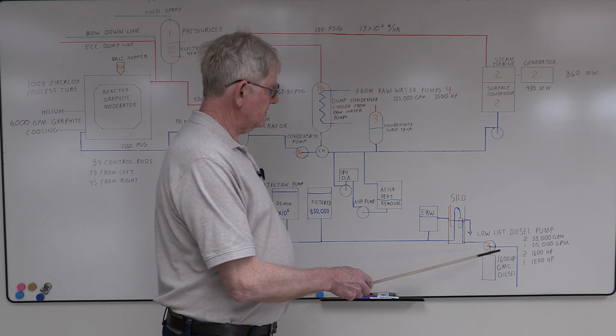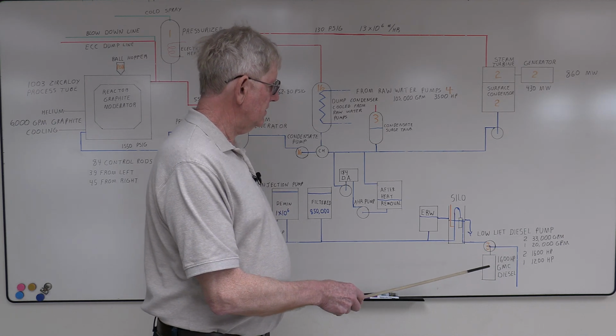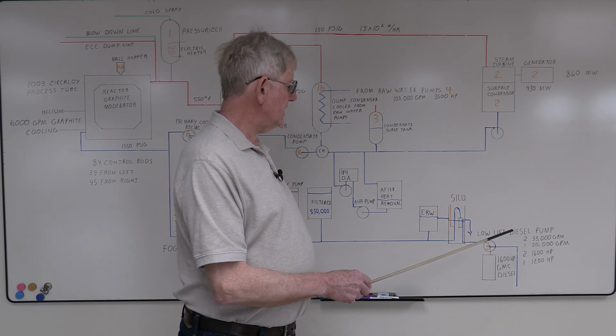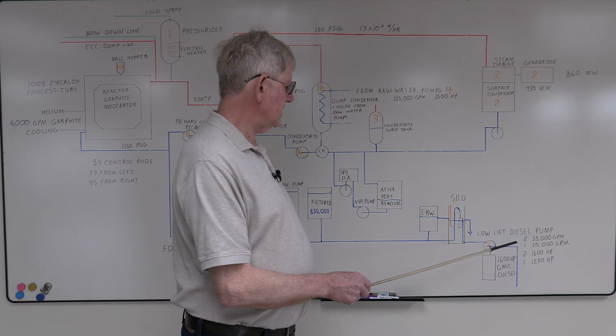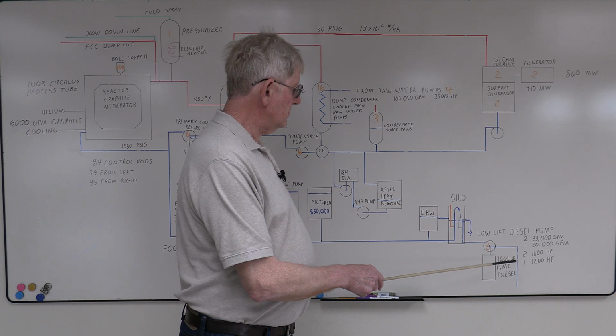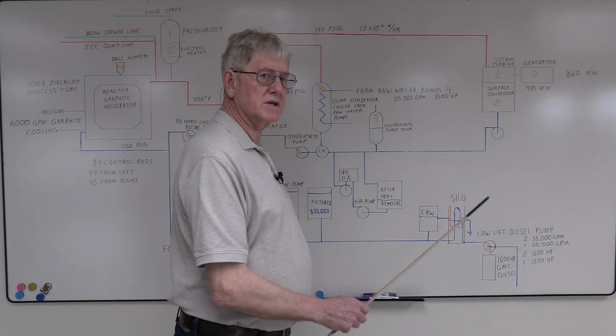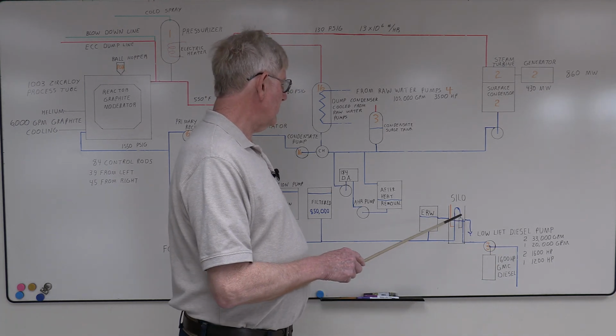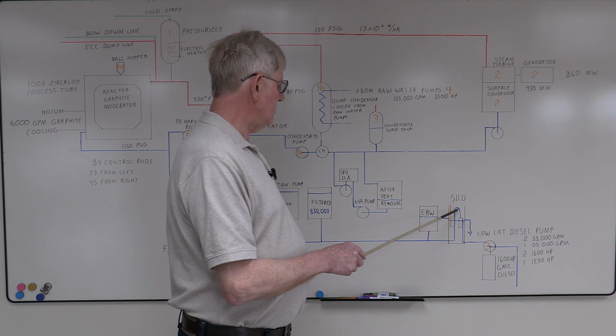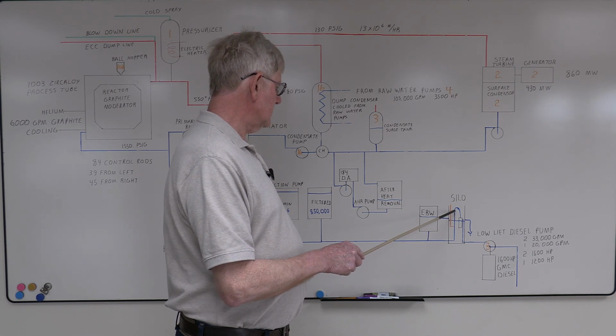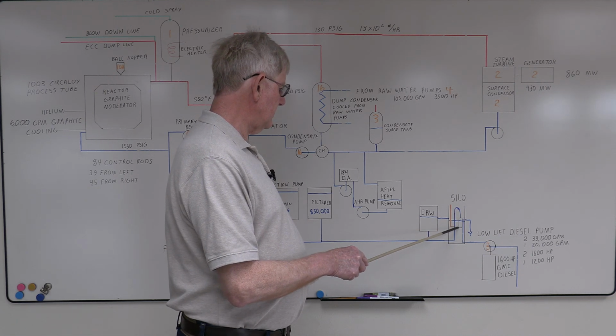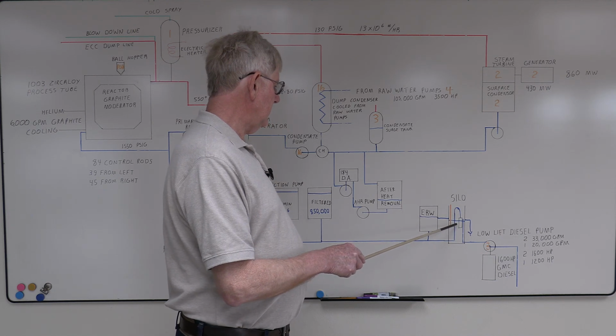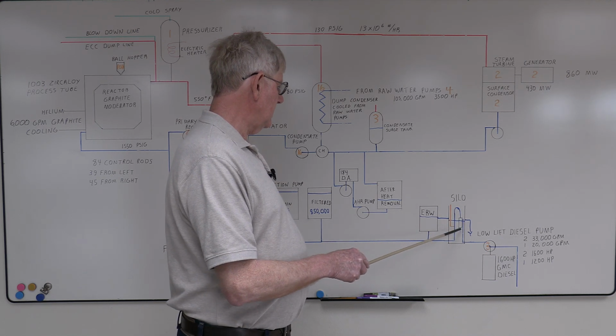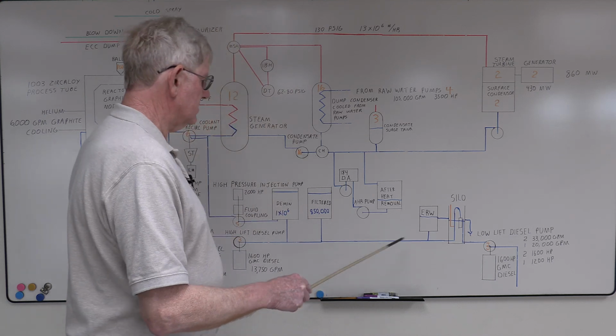You had your low lift diesel pumps. They pumped out of the river. You had two pumping 33,000 gallons a minute and one at 20,000 a minute. Same engines. One was a 12-cylinder, everything else was 16 cylinders. The way the silo worked, you had an air bubble in the pipe here. As this level dropped, the air bubble would move up, the water would come up, and then it would vent the air bubble out, and then this would siphon raw water into the system.